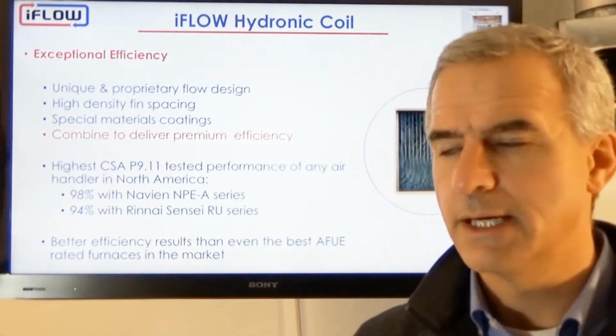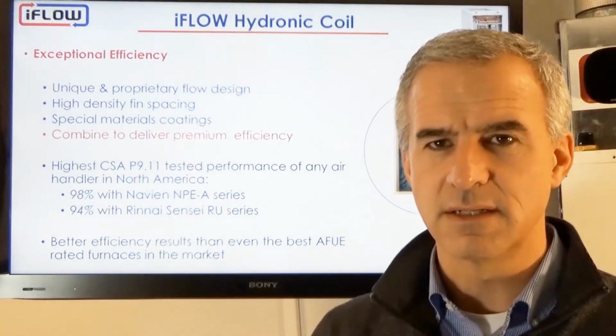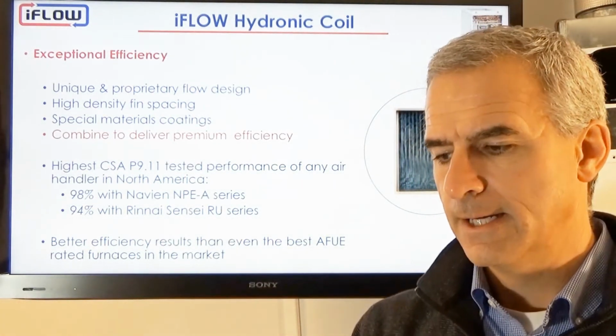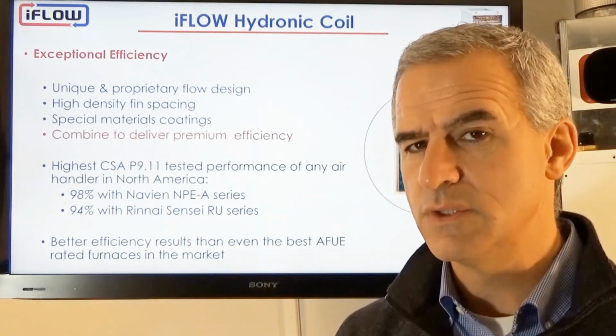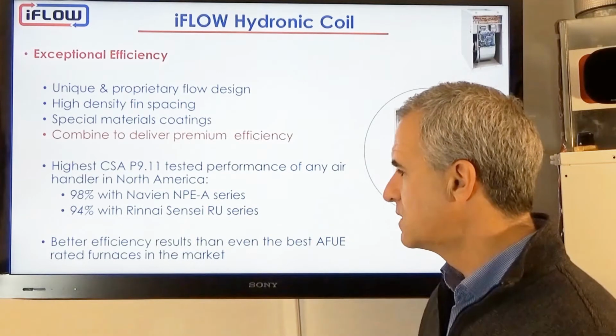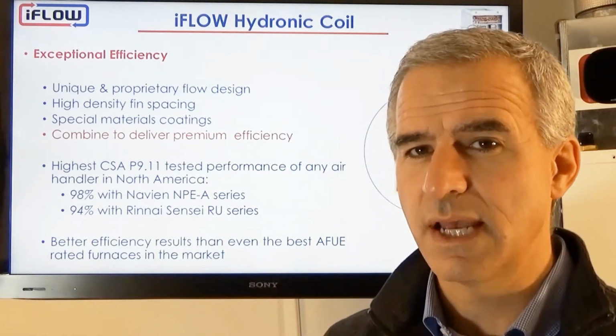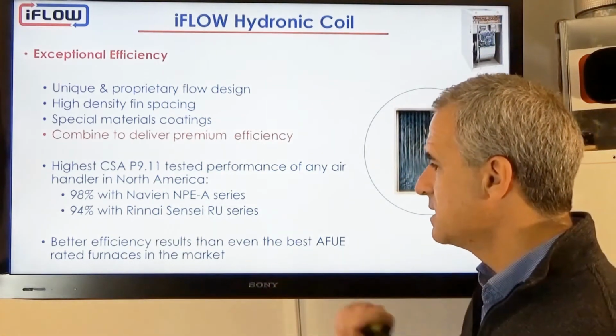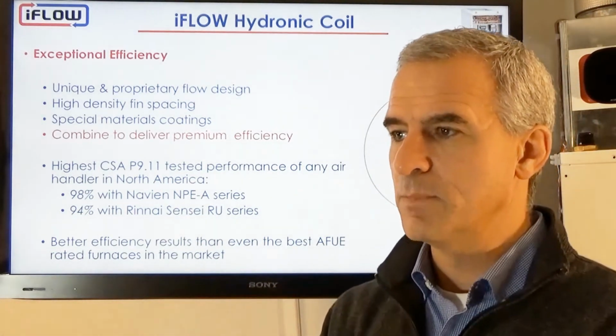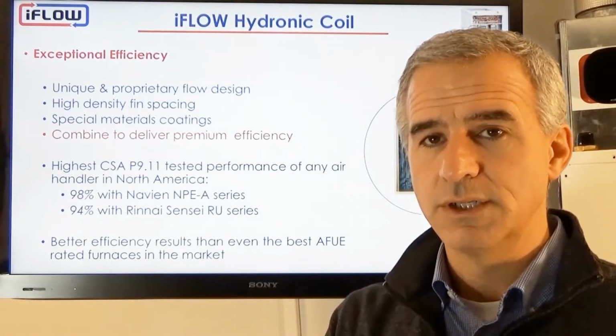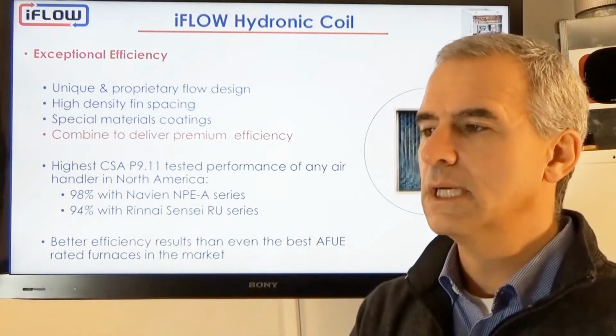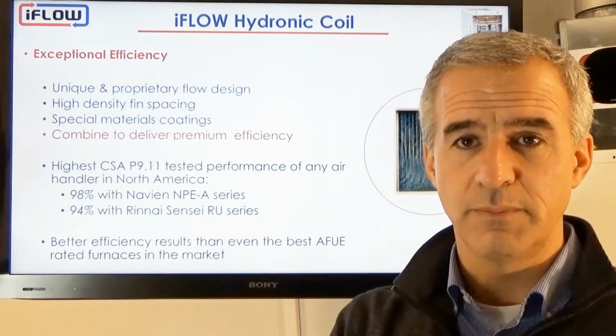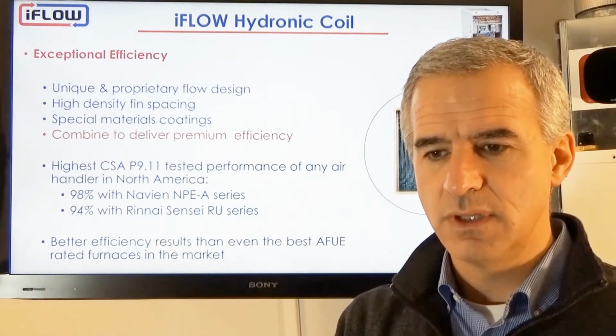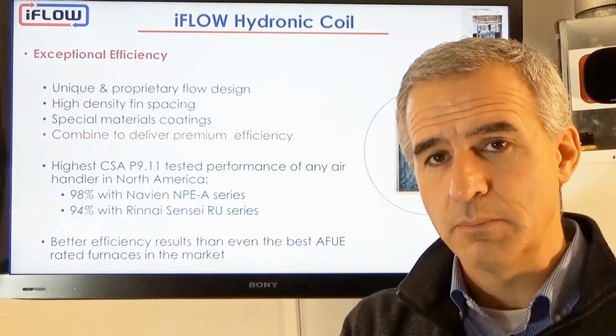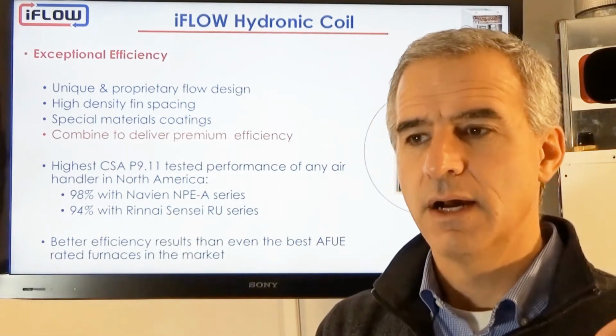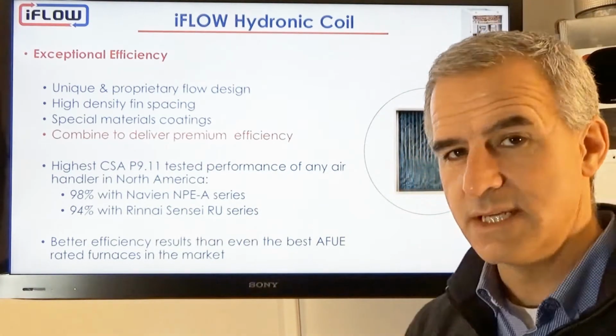We've also recently been the subject of a couple of reports that have tested our units as they compare to a 95% AFUE 2-stage furnace, and in those cases we have performed even better than those furnaces, up to 15% better. The reason is that most furnaces have a limit to the minimum modulation, the minimum speed they can go, if you will. Depending on what appliance we pair with to do the heating, we can actually run at much lower inputs, providing less cycling, more comfort, and more steady temperatures, so better efficiencies.